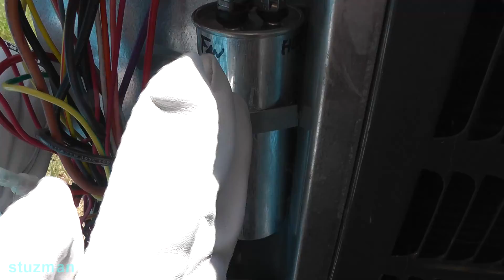It's a dual capacitor. Some of them will be round, as it is in this case, a cylindrical shape, and some of them might be an ellipse. But this is what it's going to be. Now we're going to have one capacitor, and I wrote it here. It's a fan. So this here is going to the start winding. Sometimes that's also called an auxiliary winding because the capacitor stays in place even after it's started.